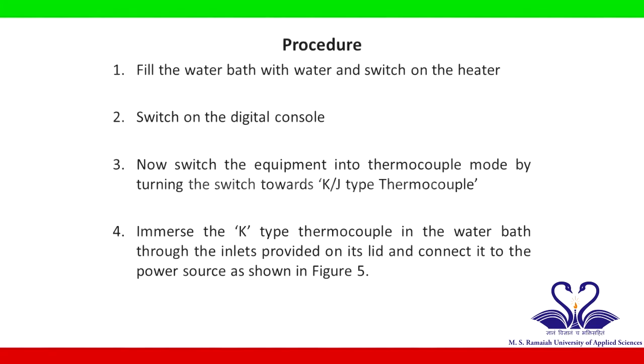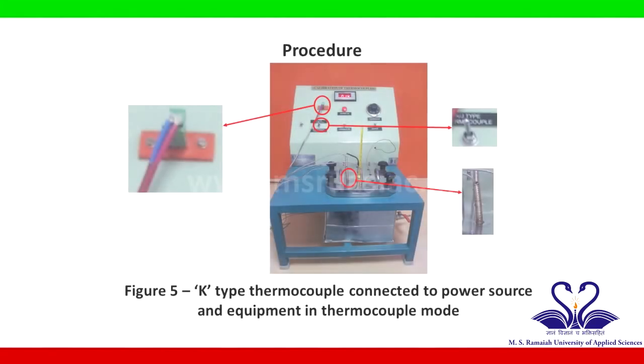Here goes the procedure for carrying out the experiment. Initially, fill the water bath with water and switch on the heater. Switch on the digital console of the equipment. Switch the equipment to thermocouple mode by operating the equipment mode switch. Immerse the K-type thermocouple in the water bath through the inlets on the bath lid and connect it to the power source as shown in figure 5.